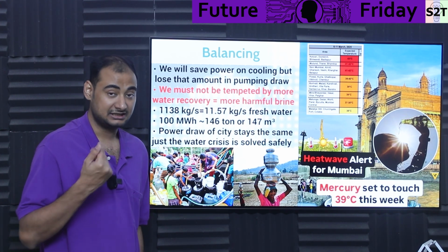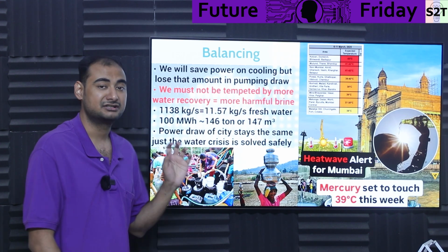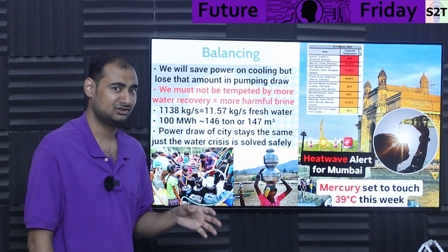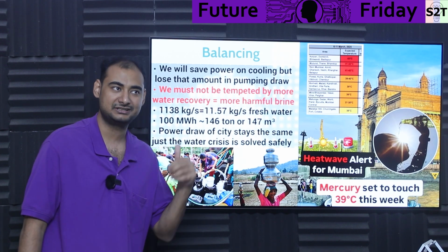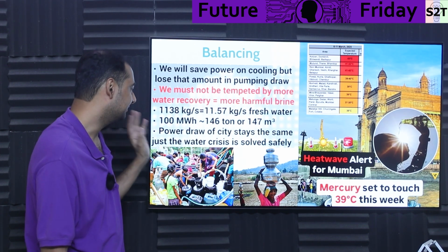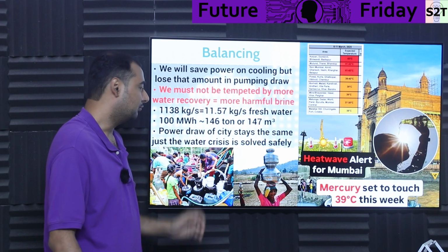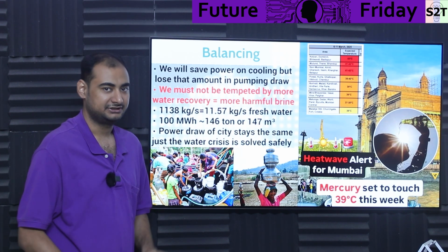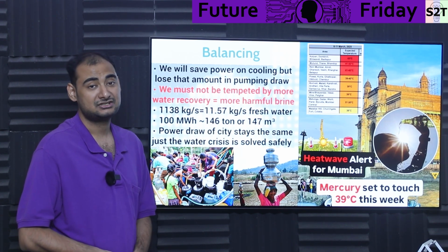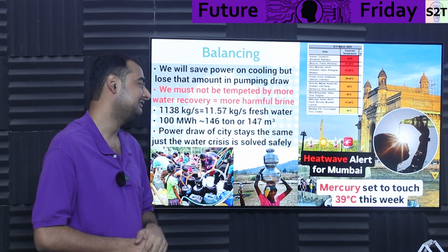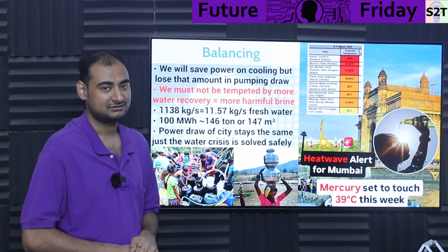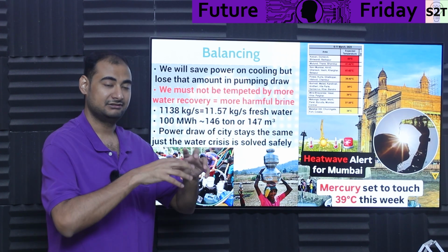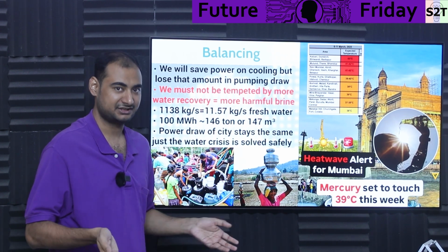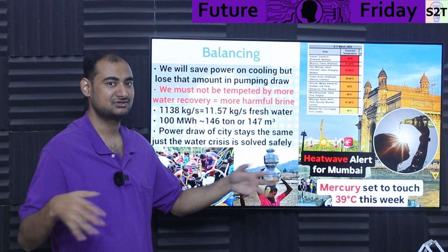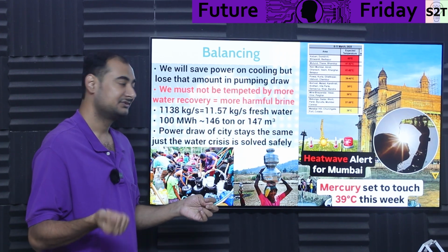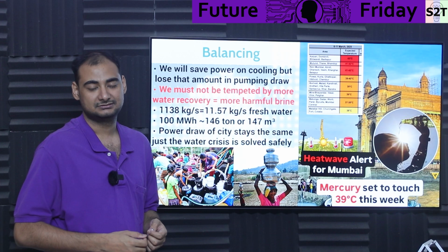Now what does that translate to? With current systems, if you have 100 megawatt hour, a very small district cooling system, since most district cooling easily exceeds that, 100 megawatt hour will give you 146 tons of water, give or take. That's such a large number we have to use cubic meters, 147 cubic meters of water. That's reservoir level water, meaning when you measure reservoirs you measure in cubic meters, and giant dams in cubic kilometers. So here it is so much.